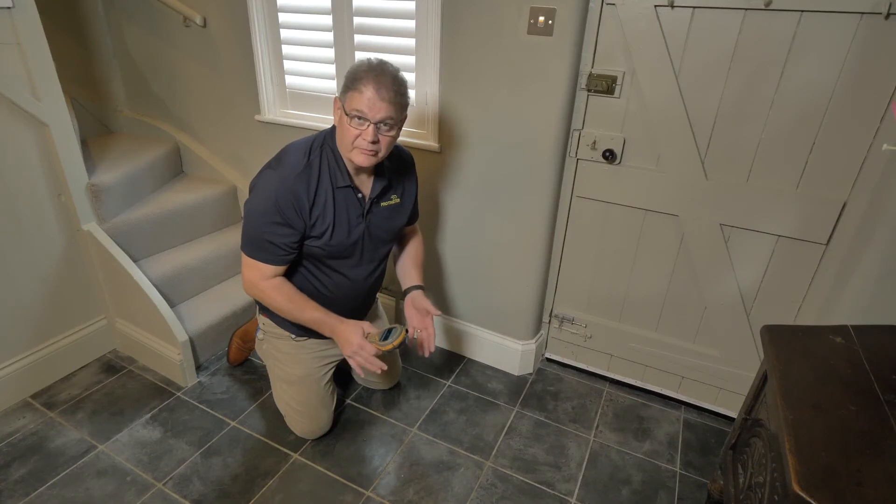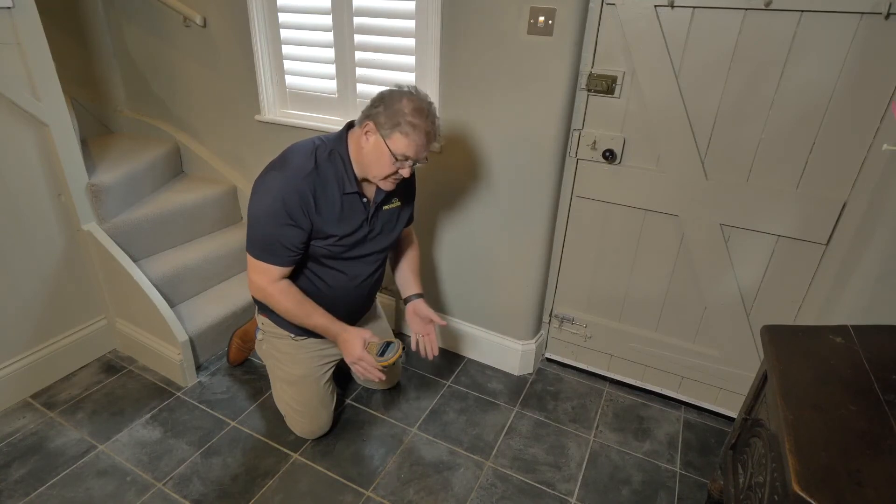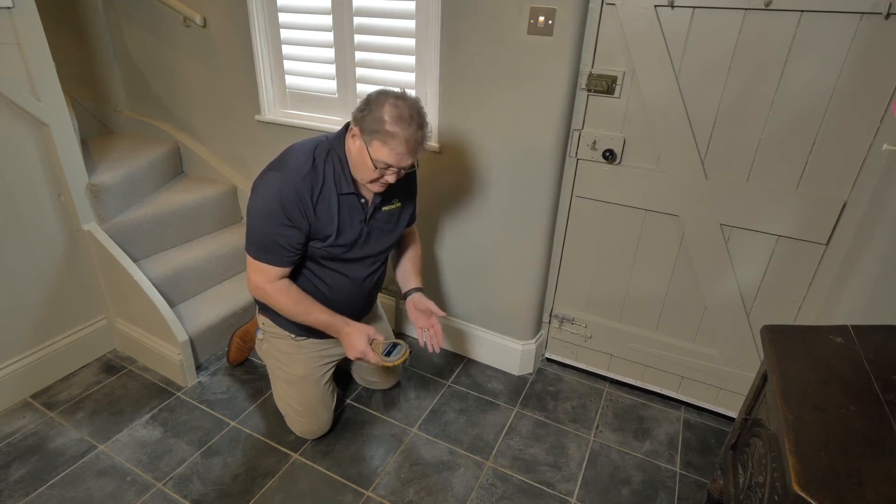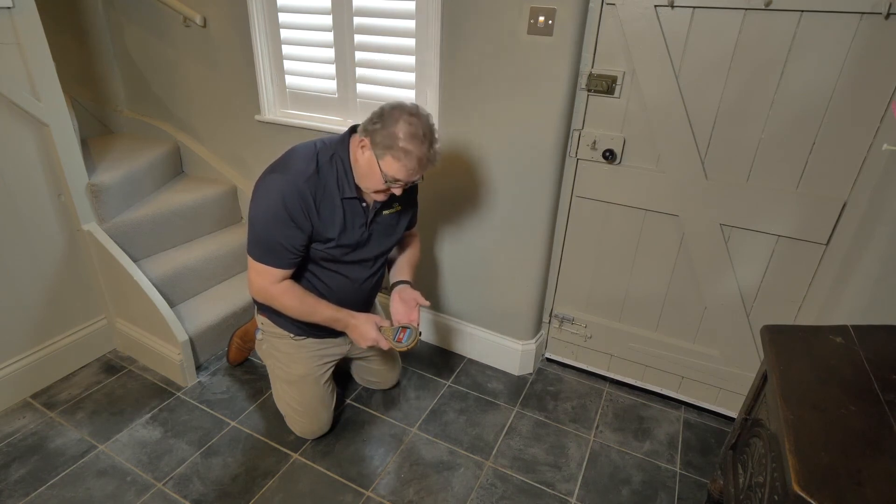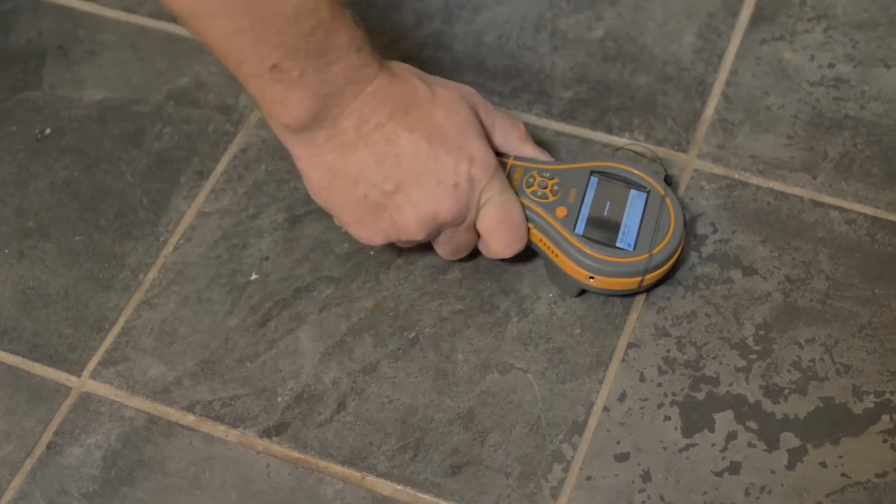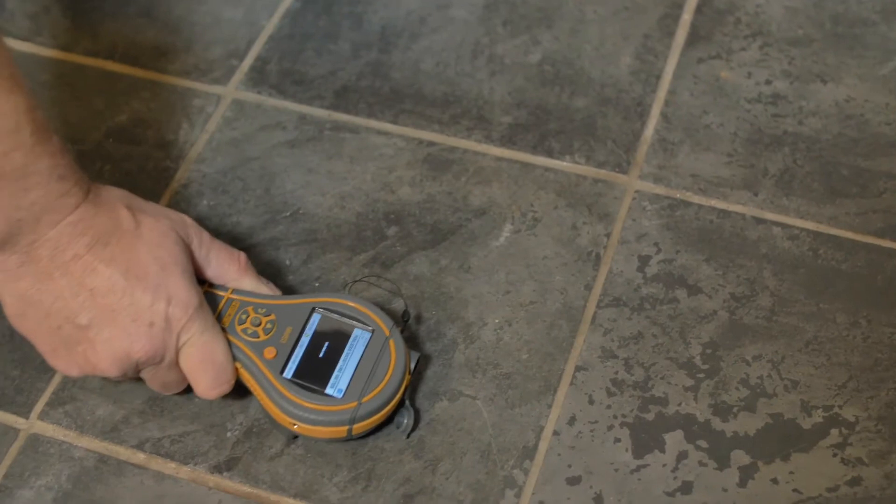Often you can't see the presence of moisture. For instance, on this tiled floor, there's no visual indicators of excessive moisture. But switching to the non-invasive mode, we can actually look for moisture behind this tile, and indeed, we can find excessive moisture here.